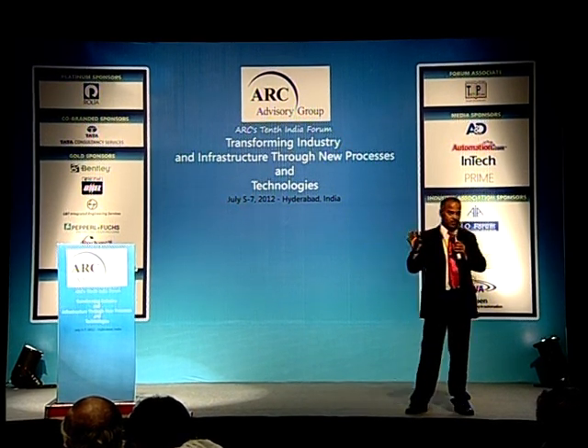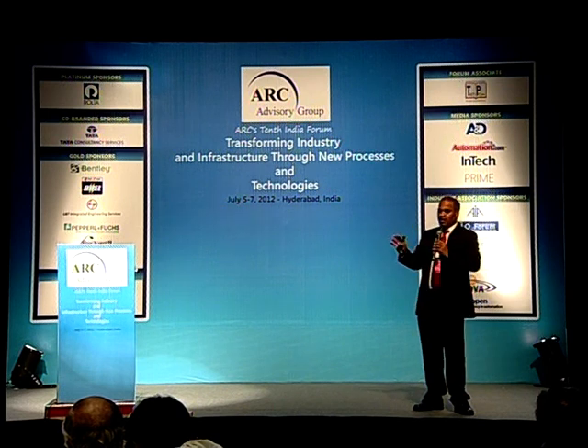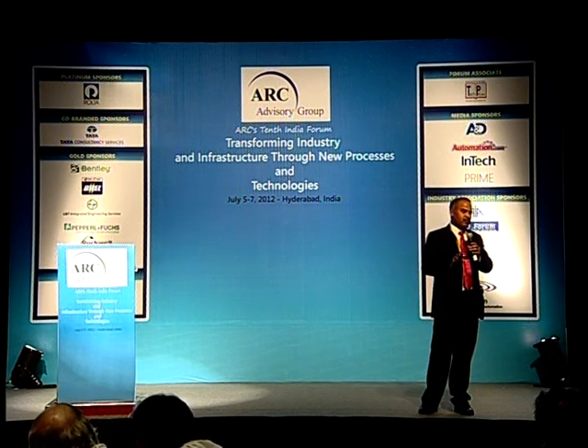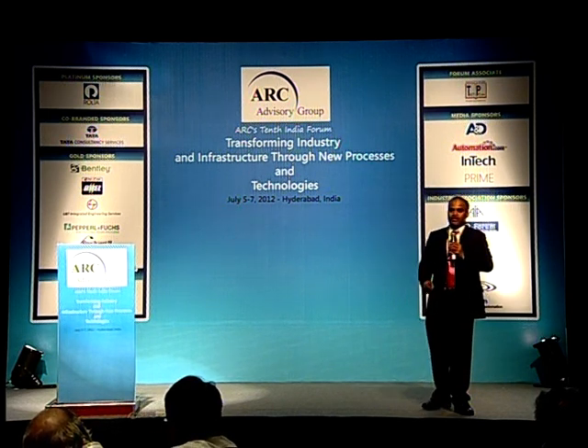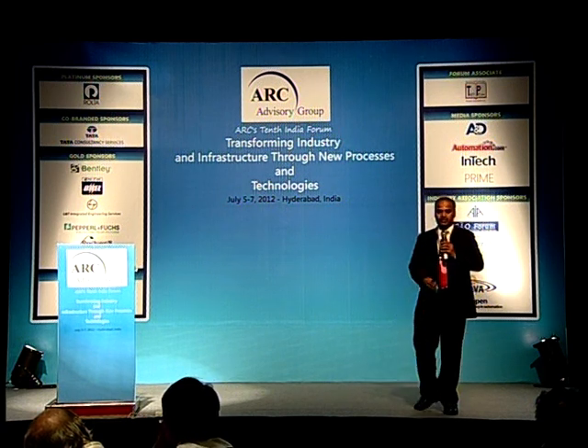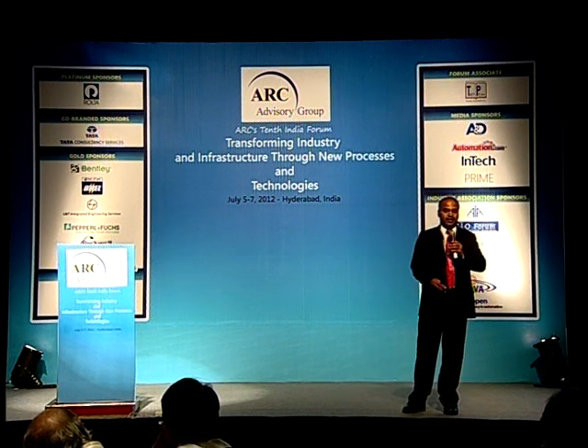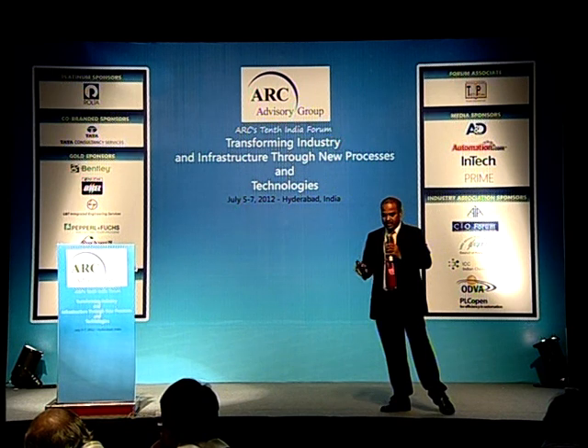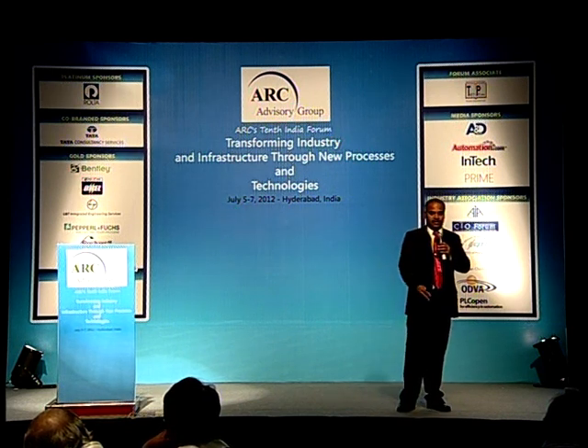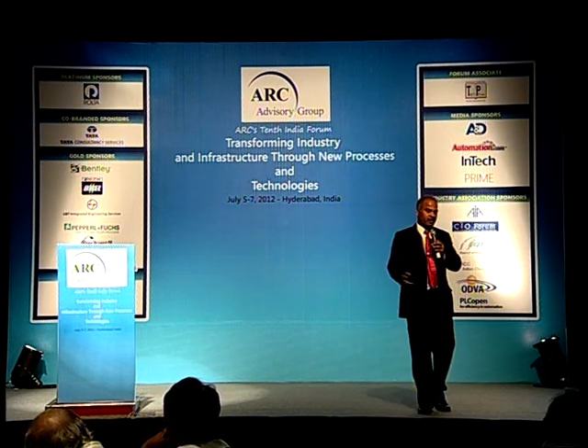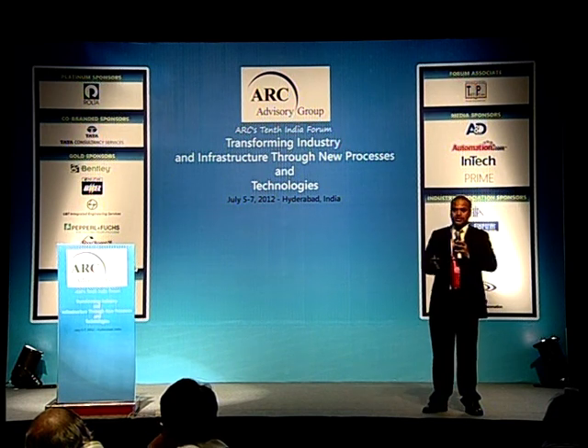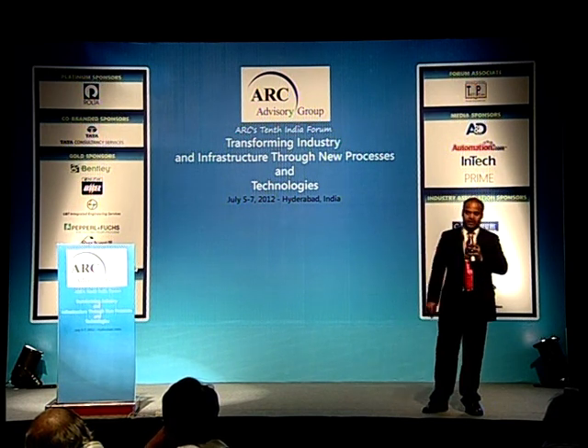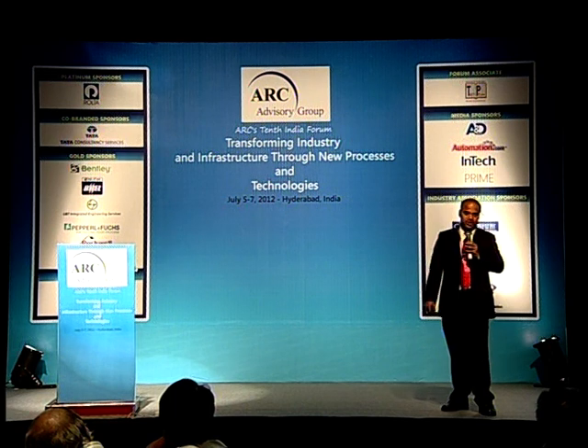So especially when we talk about ignition source, most of the time we mean the electrical source of ignition. When we bring energy into the field to power some devices, especially in the chemical industries, oil and gas, where the area is classified as a hazardous area, we have to limit the energy. And this method, of course, works very well for what we call the conventional method.